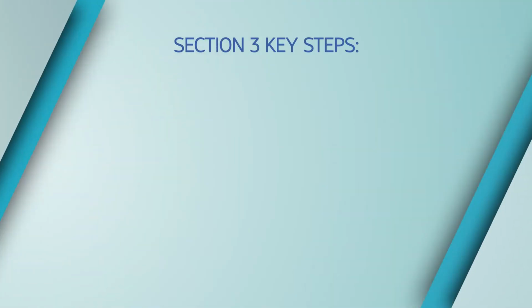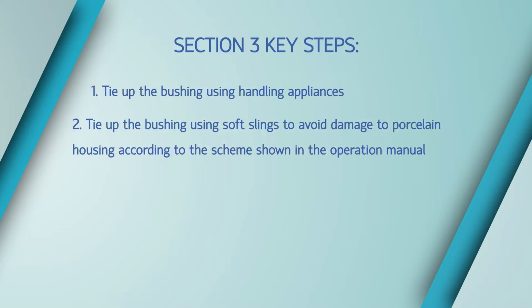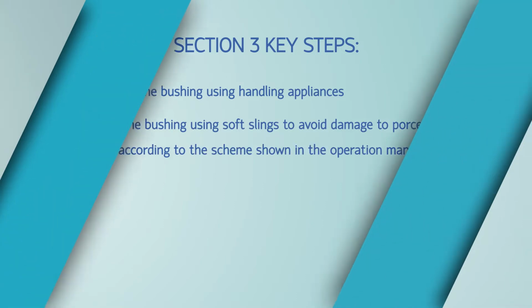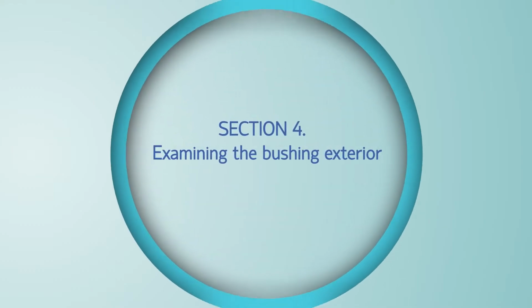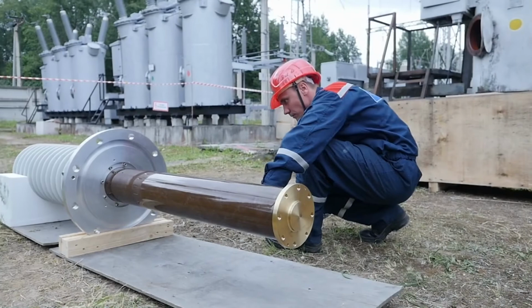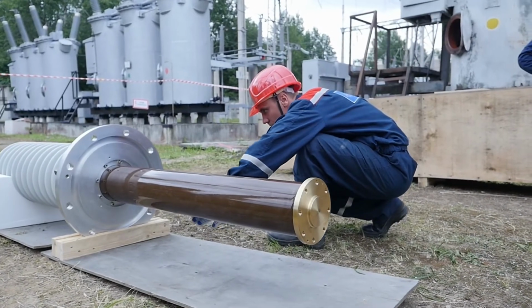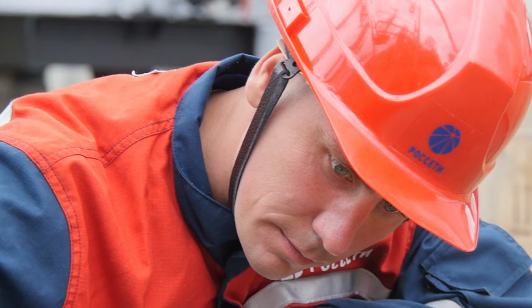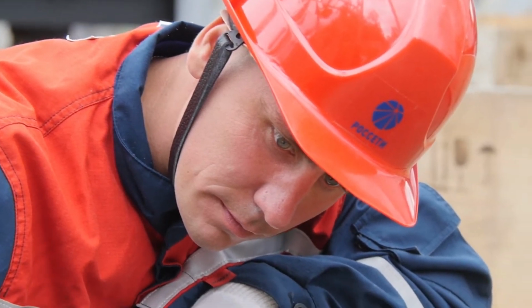Let us go through the key steps again. Tie up the bushing using handling appliances. Tie up the bushing top between the second and fifth sheds of the housing. Examining the bushing exterior. Examine the bushing closely for any porcelain housing and bottom damages. Pay special attention to housing cleavages.